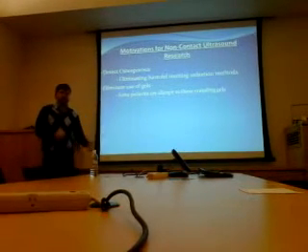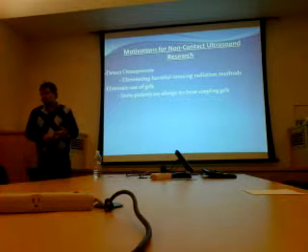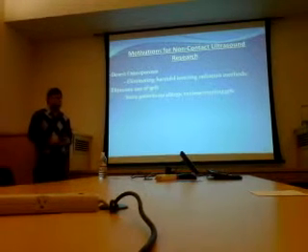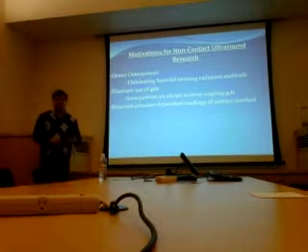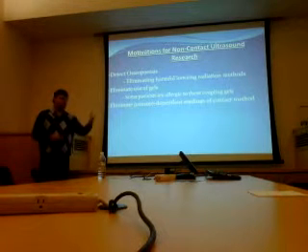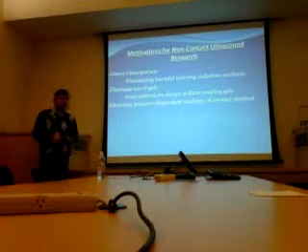And I've read recently in certain papers that these coupling gels have been known to cause pneumonia and infections, and they're also temperature dependent, so there's a sort of error associated with these coupling gels. Non-contact ultrasound would eliminate the use of these coupling gels. It would also eliminate pressure-dependent readings of the contact method. When I apply a transducer to a subject, I'm going to get different readings because we're going to apply different pressures. So the contact method is operator dependent, and non-contact would eliminate that.